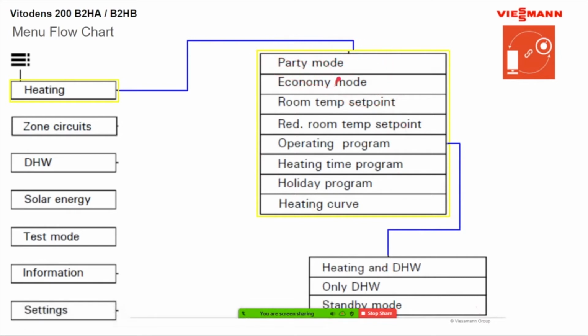Party mode, as we know, Germans like to drink a lot of beer, but that's not what it means. Party mode is if you're doing, say, a reduced temperature mode on our boiler. So at night you want it to go down to 64 degrees. What this allows you to do is go down, hit the party mode, click OK on that, and it allows the boiler to run its normal operation for 8 hours, and then it reverts back to that reduced mode.